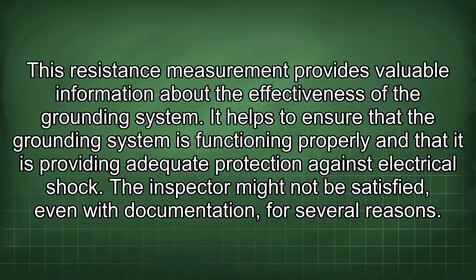This resistance measurement provides valuable information about the effectiveness of the grounding system. It helps to ensure that the grounding system is functioning properly and that it is providing adequate protection against electrical shock. The inspector might not be satisfied, even with documentation, for several reasons.